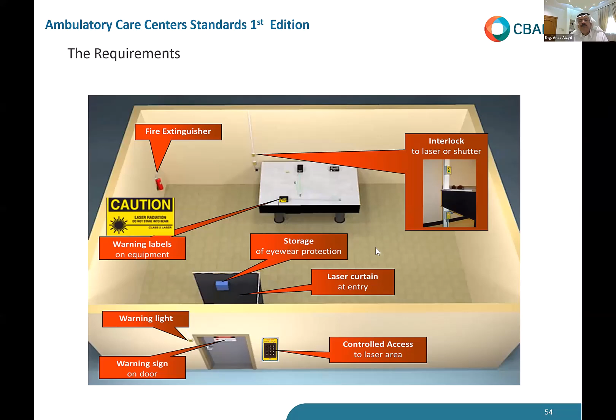There's no shielding requirement for the laser room, by the way. Plus, I think you don't use any reflective material in the room. Please make sure there are no mirrors or any reflective stainless steel in the room, because you don't want any accidental laser reflection. And last but not least, there is an implemented process to keep radiology equipment in safe, functional condition. An operation and service manual is available for the equipment. I think this is very basic.